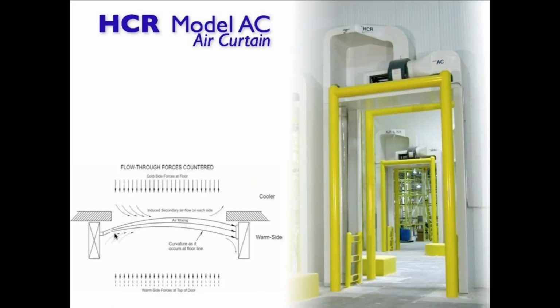And next most important slide, I don't know how many of you have come across. I will not go into too much detail, but there is a company in Europe, HCR model curtains. These curtains are hot air curtains. So the outside air is circulated, which is hot air. Now you know hot air has a higher ability to absorb moisture than cold air. So hot air absorbs the moisture and the moisture does not enter at all into your cold room. These are very expensive. I've just gone through the literature, but in India, I have not used it anywhere.